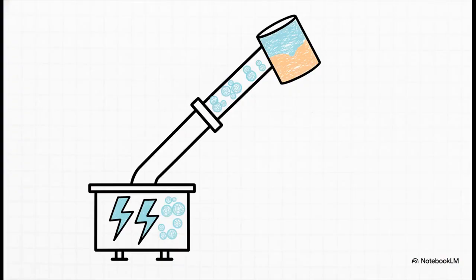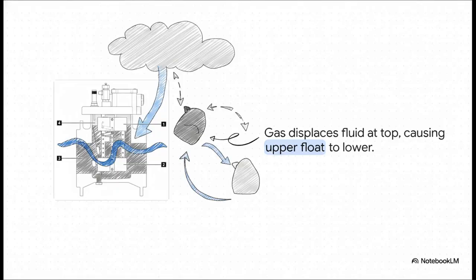Moving on to Section 2, detecting gas accumulation, the slow buildup. So picture this. Inside an oil-filled transformer, if you get an electrical fault, it can actually cause the insulating oil to break down and literally form explosive gases. Now, because gas is lighter than oil, it naturally migrates upwards. And because of exactly where our relay is positioned in the piping, all that gas collects right inside the top chamber of this device.